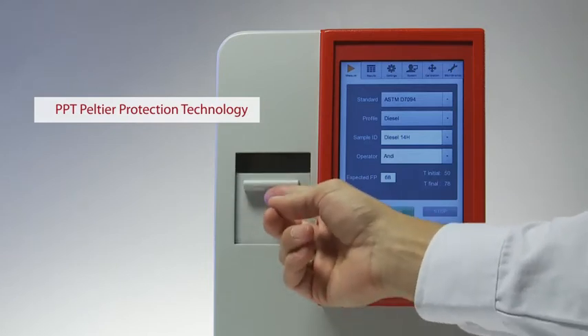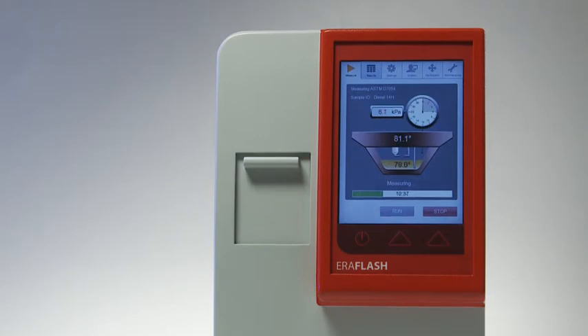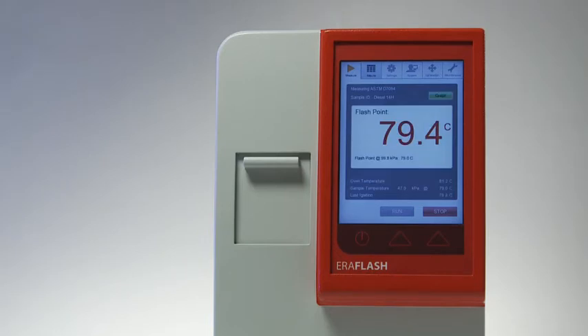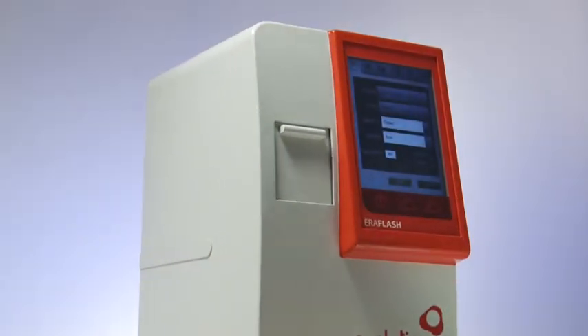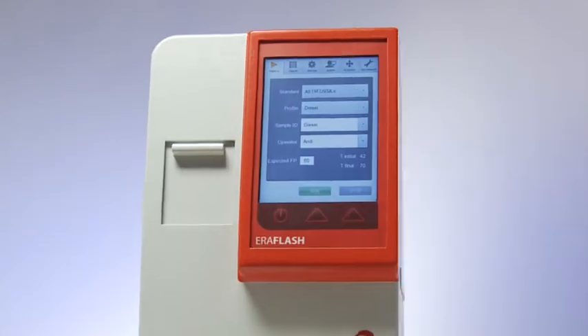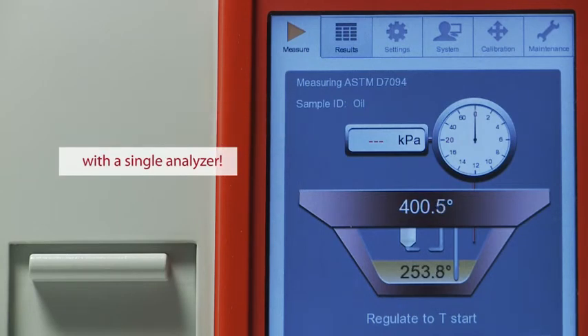ERAFLASH's innovative PPT Peltier Protection Technology, a patented Eralytics innovation, allows for previously unmatched heating and cooling rates. The resulting turnaround times are significantly shorter than those of all other available flashpoint testers. Additionally, the unique PPT design makes ERAFLASH the first and only flashpoint tester on the market to cover the full temperature range of minus 25 to 420 degrees Celsius with a single analyzer.